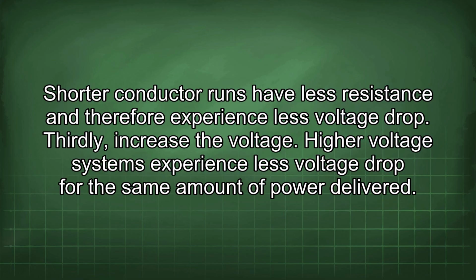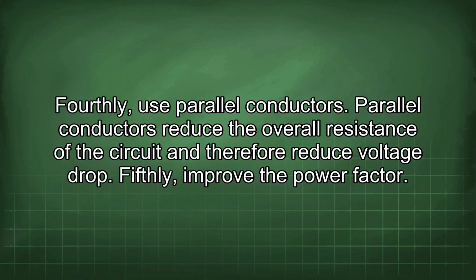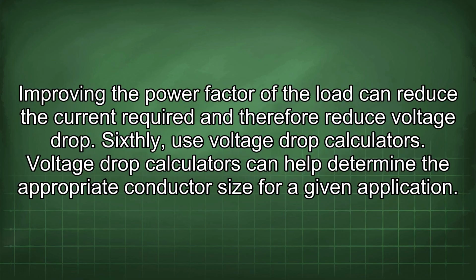Thirdly, increase the voltage. Higher voltage systems experience less voltage drop for the same amount of power delivered. Fourthly, use parallel conductors. Parallel conductors reduce the overall resistance of the circuit and therefore reduce voltage drop. Fifthly, improve the power factor. Improving the power factor of the load can reduce the current required and therefore reduce voltage drop.